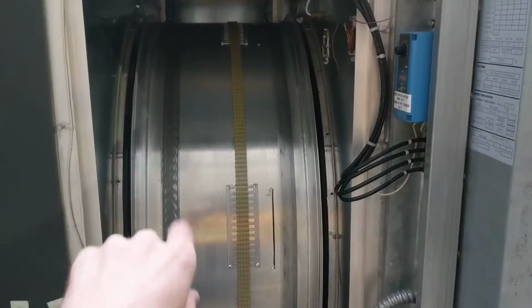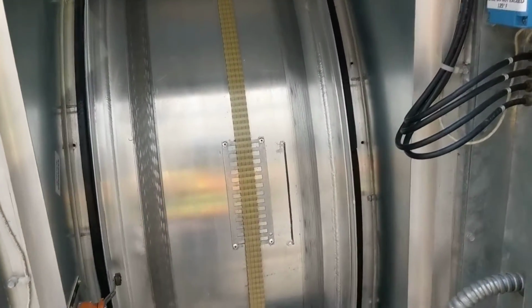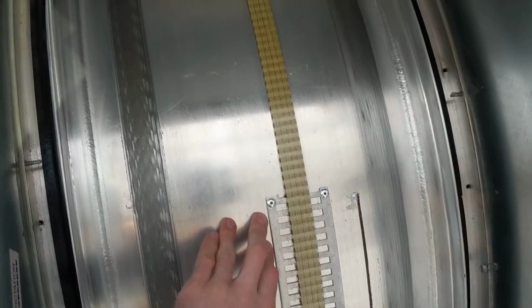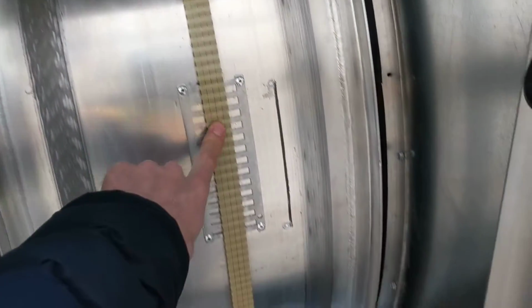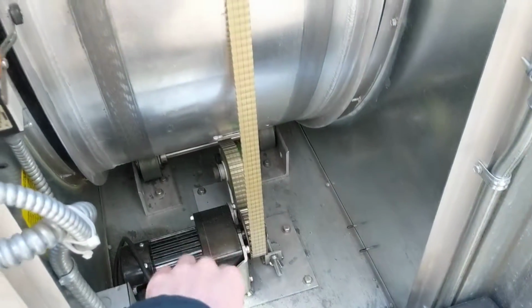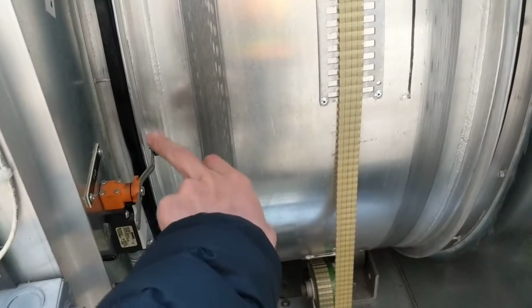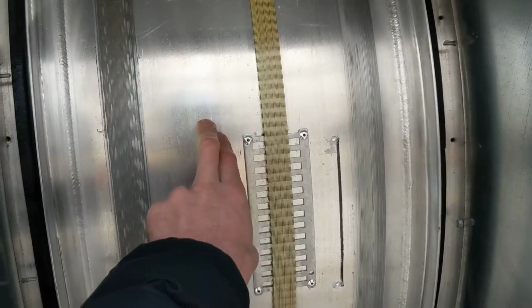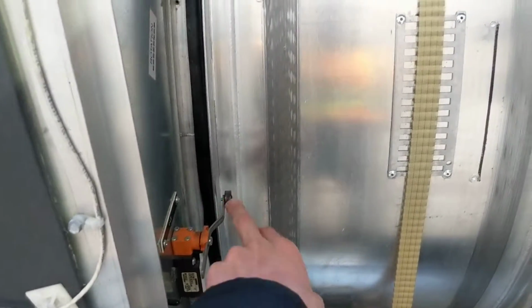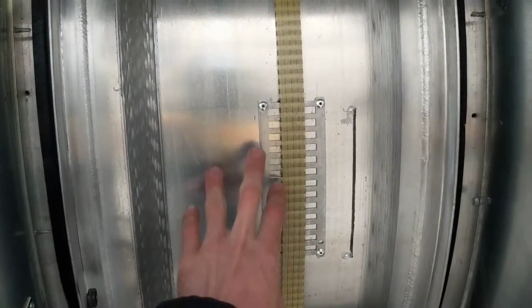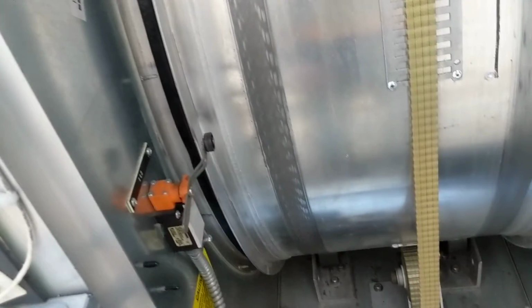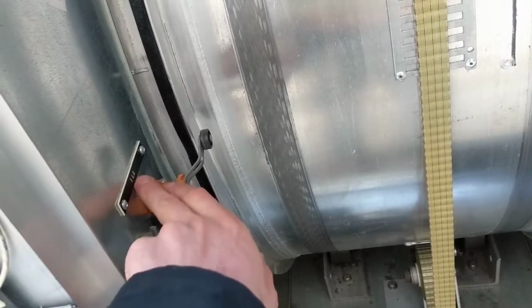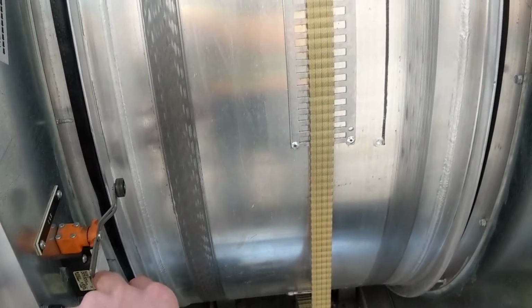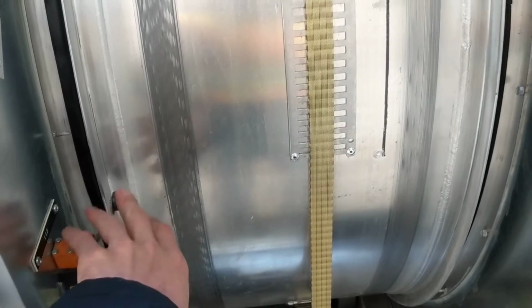This here is the heat wheel, or sorry, I should call it the desiccant wheel. So this wheel spins by this belt that's driven by this motor, and this is a switch to verify that the wheel is spinning. That's a safety mechanism, because if the wheel's not spinning, then you can have these burn up. Apparently units have caught on fire. So this switch, see it's labeled over here, that's going to correspond to your wiring diagram. And if for some reason this has come loose or something, this isn't engaging, that'll shut the unit down.